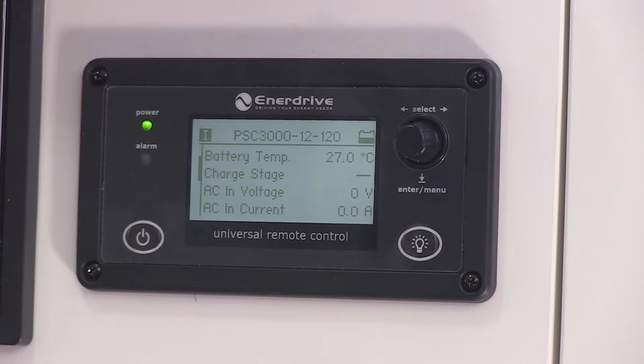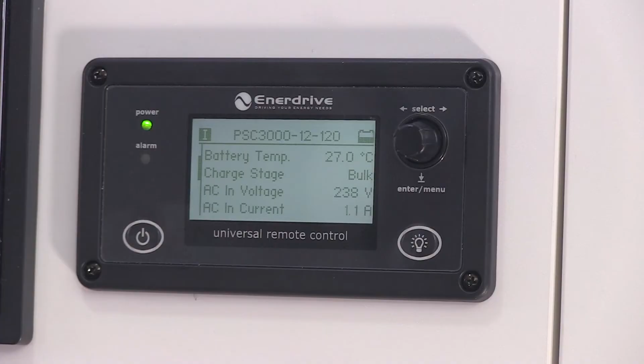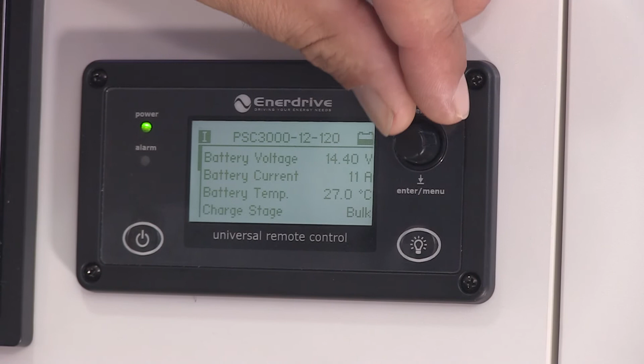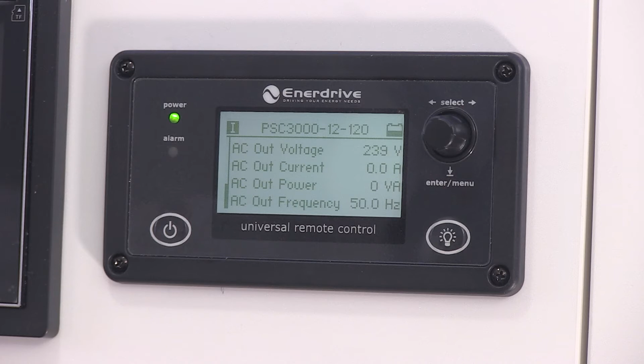So where this is a powerful tool, for instance, is if you're plugged into a powered site and things aren't working - what better way to confirm if you have the issue in your build or if the issue is in fact on the power pole than to walk up here and simply say, well, I know I'm plugged into mains power, but at this given time, I have 0 volts coming into this van. There is no power off the grid. So then you need to go back outside and look for the issue with your extension cord or with the park operator - there's obviously an external issue. So this is quite a handy tool for the user if you understand your van properly.